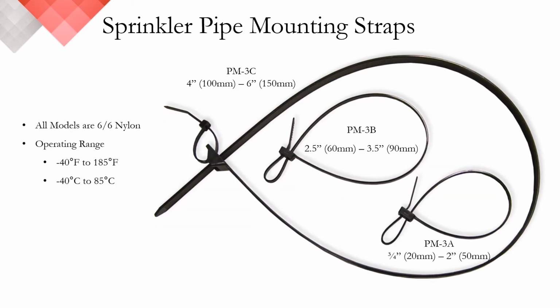If and or when you can install Protectowire on the ceiling sprinkler pipes, do not use standard zip ties. A standard zip tie can easily be over-tightened and mechanically damage the detector. We offer 3 different sizes of 6/6 nylon, heat-stabilized, double loop pipe straps designed specifically to meet the needs of sprinkler pipe installations.